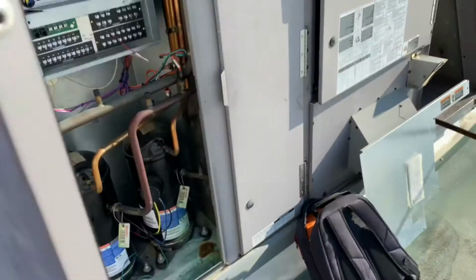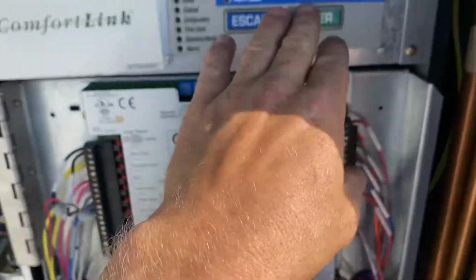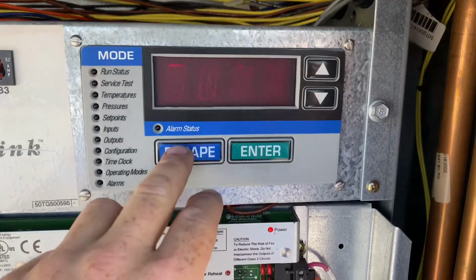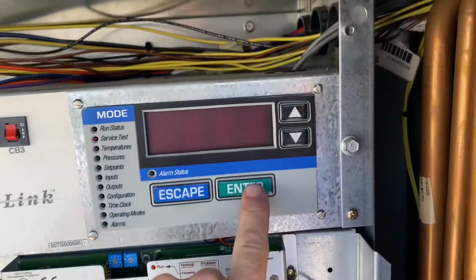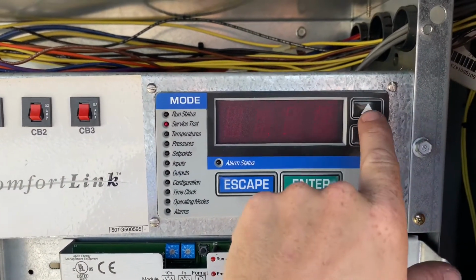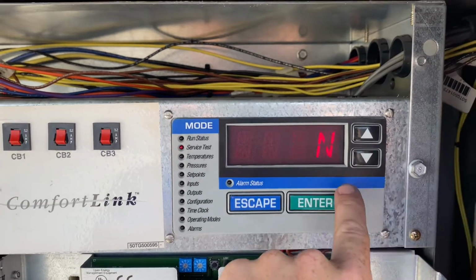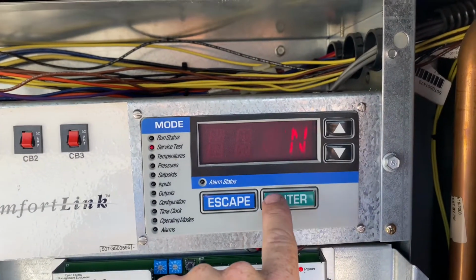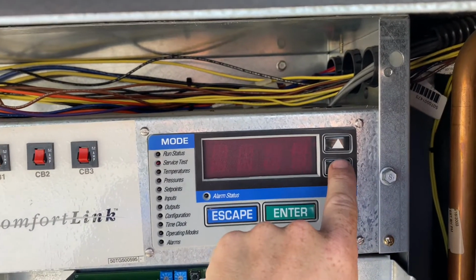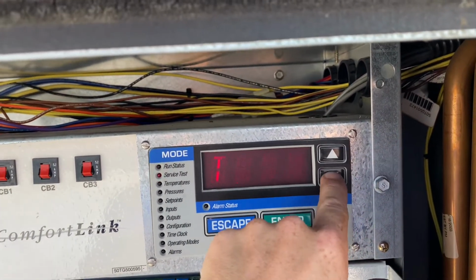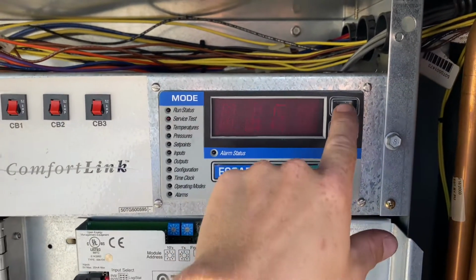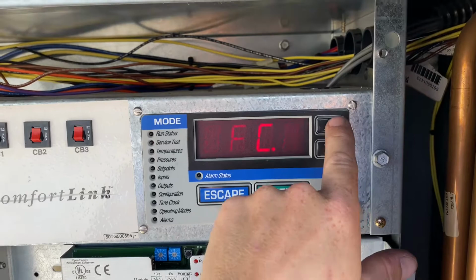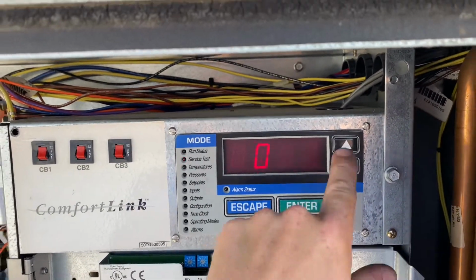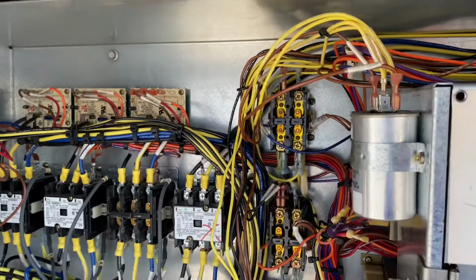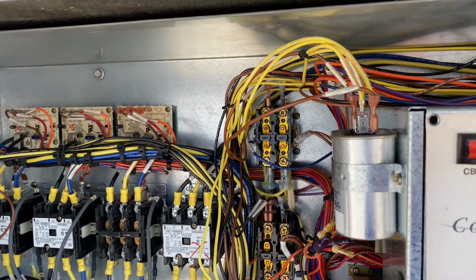So she's on. Power's going to the communication board. So now power's to here. I will escape out, go down to service test, enter test mode, enter again, turn it on. Okay, now it's in test mode. Escape out, go down to fans, enter indoor fan, nope, outdoor fan. I'm gonna go outdoor fan 1, turn it on. It pulled in the fan, outdoor fan contactor 1.